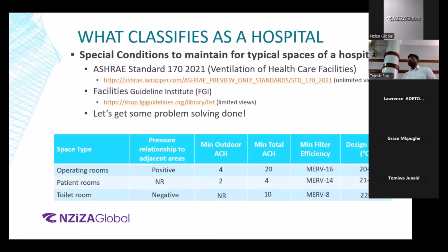NR, I said, is not required. It can be positive as well. If negative is fine as well, but make sure that if the patient room has an attached toilet room right next to it, the patient room as compared to the toilet room needs to be positive, right? We don't want it to be negative because we don't want the toilet air to come into the patient room. Toilet room, unclean air, right? So that makes us come to the next point, regarding the toilet rooms. Whenever you have a toilet room, trash room, that will always be negatively pressurized as compared to the adjacent areas.